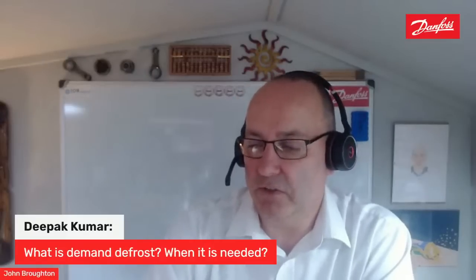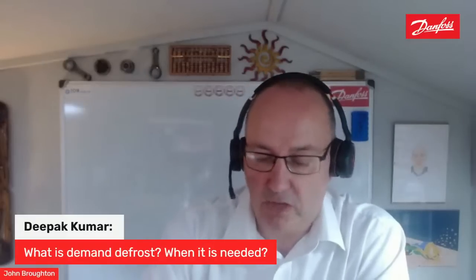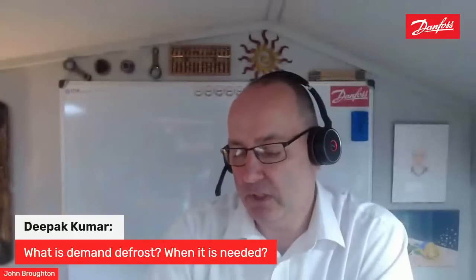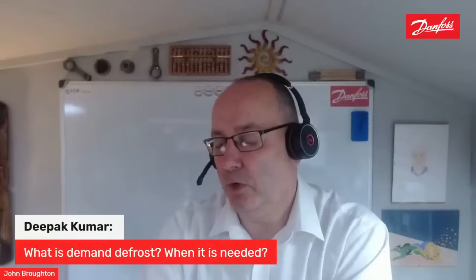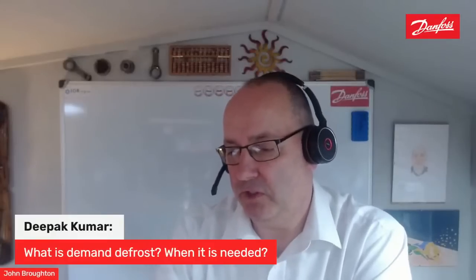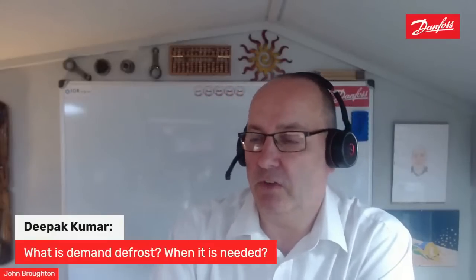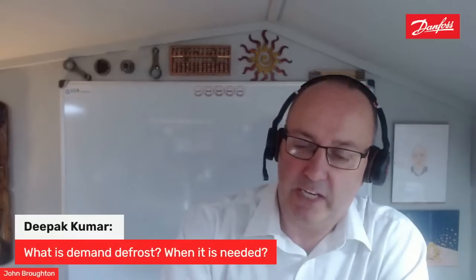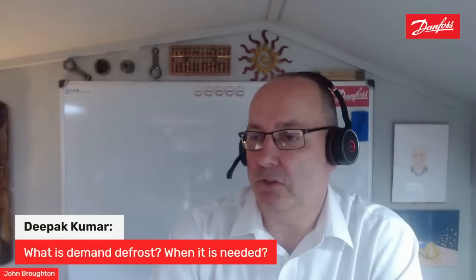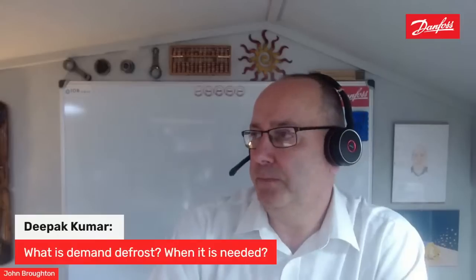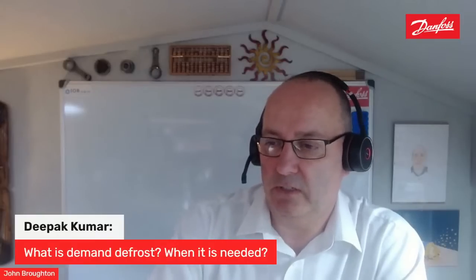And it's a very good way to save energy, because that defrost heat that you put into that room has to be removed by the refrigeration system. So that's one energy saving, but then you're also saving the electrical energy of using that defrost heater as well. So that is a good function.